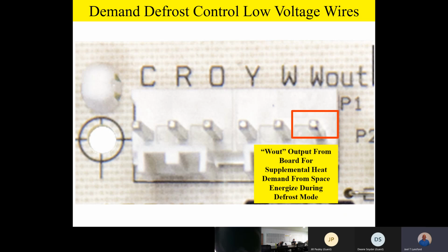But during normal operation, if you go to auxiliary heat, it's going to loop the W through the W out. But during defrost, we actually steal the Y signal to ensure that the compressor is running. We take that Y signal and loop it out for auxiliary heat. So it's just a little interlock relay that ensures that the compressor is running during defrost. So when we're in defrost, we know the compressor has to be running, otherwise we won't get auxiliary heat. And then during non-defrost operation, if we get auxiliary heat, we have to pick that up from a thermostat call actually calling for auxiliary heat. So that's the difference between the W and the W out and the Y and the W out circuitry internally.